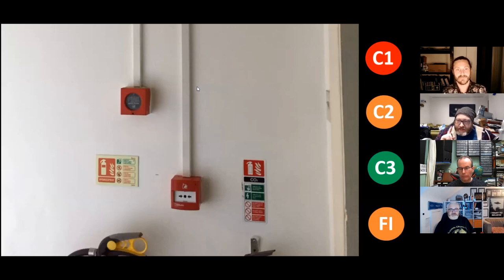I've got to be careful how many times I say assume. But having said that, Dave, I've seen before where you've had a shared entrance and maybe a floor one side to one commercial tenant, and then the other, and because they're not liaising with each other, which is part of the Regulatory Reform Order, which they should do with their fire safety, they've installed two separate systems. So when you're running out here to operate, which one do you press?